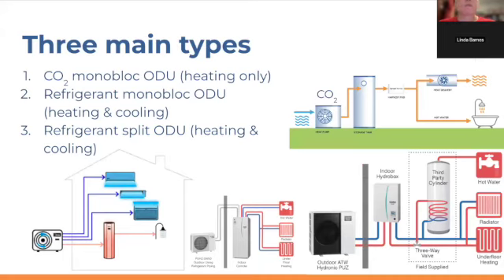So combi heat pumps fall into three main types. Like I said, there are some CO2 monoblock style outdoor units, and monoblock means that the refrigerant stays in that outdoor unit that stays outside of the home, and then a secondary heat transfer fluid, typically water or water plus some percent glycol mix, is what goes inside the home. And so installing monoblock outdoor units in a home does not require any field-made refrigerant connections. And so there's, in theory, a lot lower chance of refrigerant leaks.